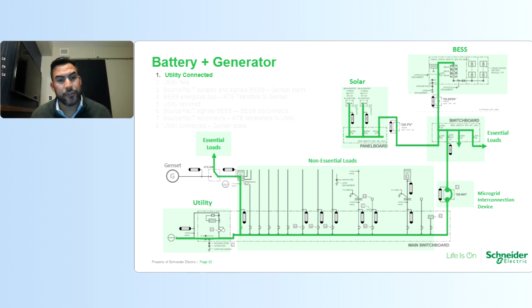The non-essential loads are the loads on the main switchboard that don't require emergency power. They can remain dark in the event of the outage. And if you go to the far right, you see the microgrid interconnection device. Upstream of this microgrid interconnection device, you see this switchboard. We can call it a critical switchboard, where you have your energy storage system, your solar system, and essential loads connected.